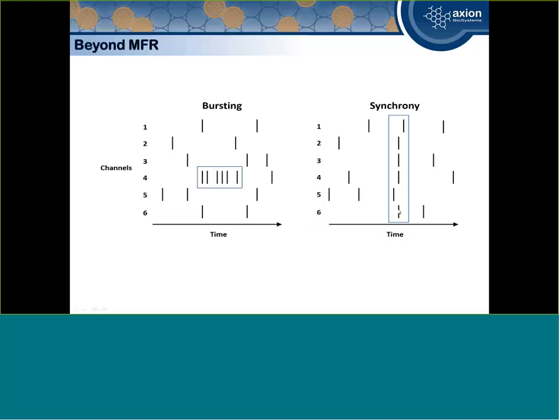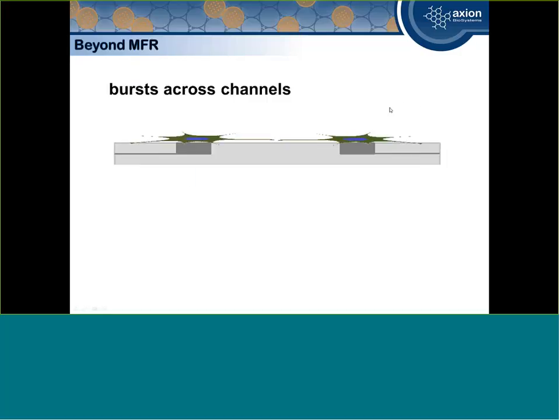Also, synchrony, which is an event that happens in space and time, where we can look at how groups of neurons that are networked together will now trigger firing events across all of them within a very short time window. And depending on how tightly bound these are temporally and across space, we get a metric called synchrony, which is just a simple metric correlating the spikes to each other. And you can only really get this in high capacity using an MEA.